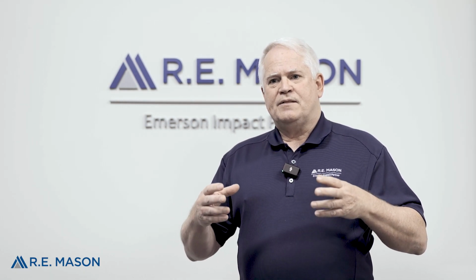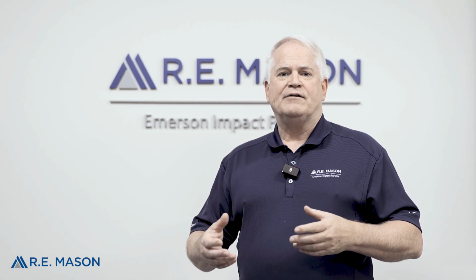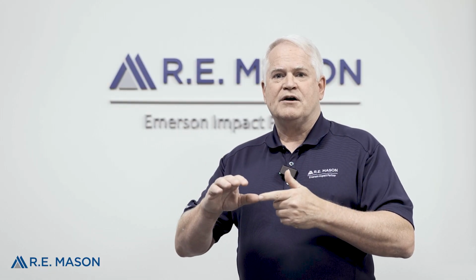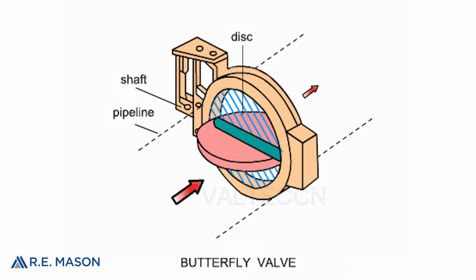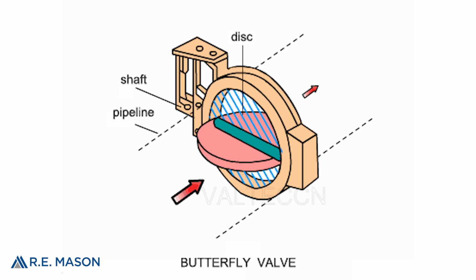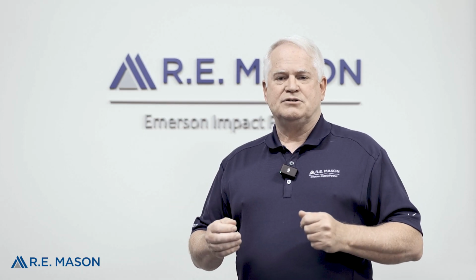Where we get the contrast to that is rotary valves like a V-ball or a butterfly valve. Whereas in a rotary valve, you see that the flow moves through the valve and the restriction in there doesn't make it go through a tortuous path. So there is a much higher recovery between the minimum pressure as it goes through the vena contracta and the recovered pressure. So it's a high recovery valve and thus has a tendency for greater cavitation issues.